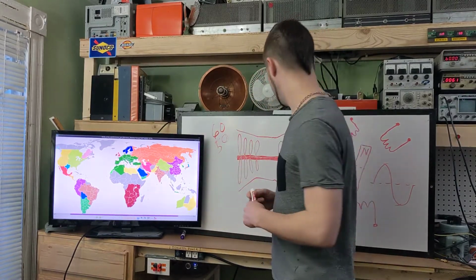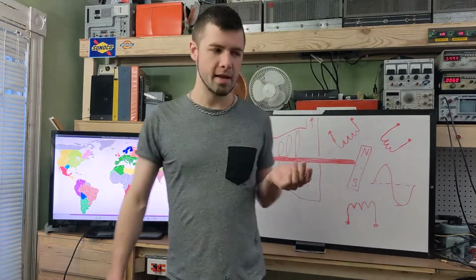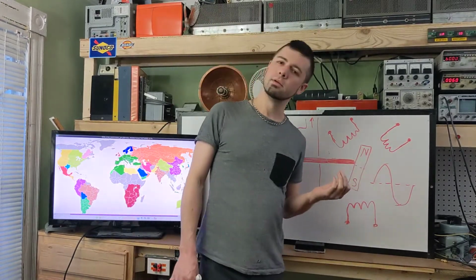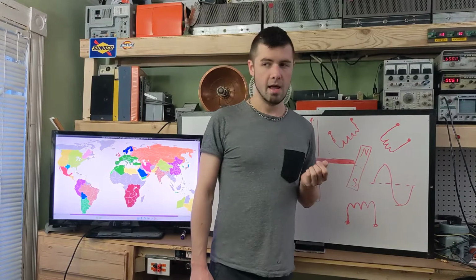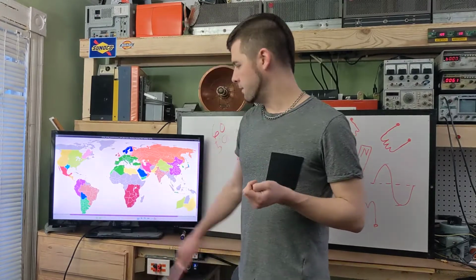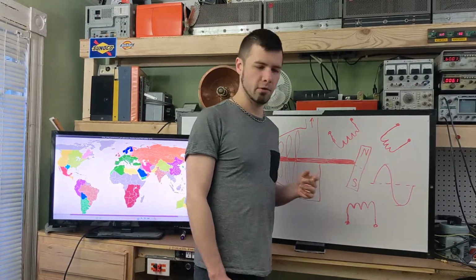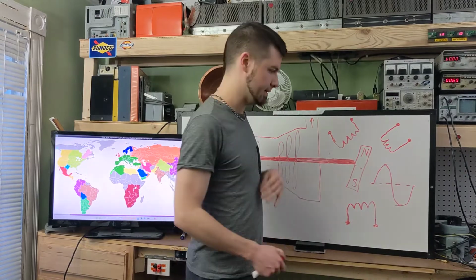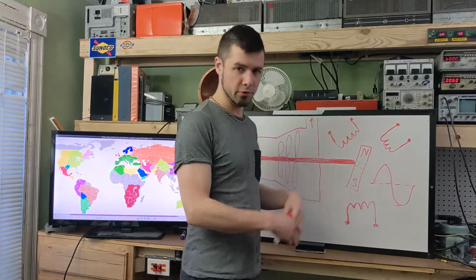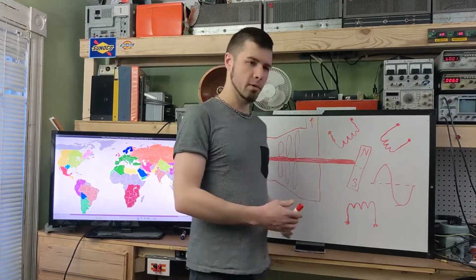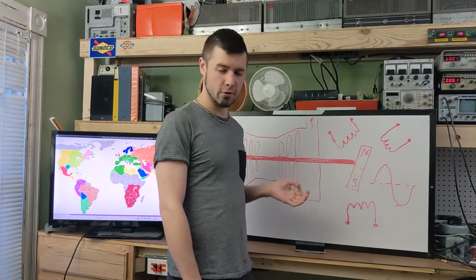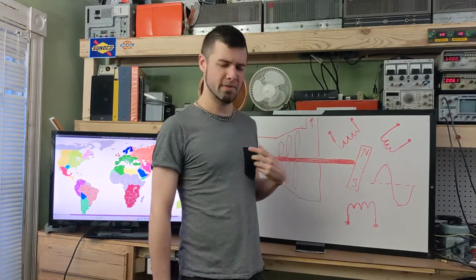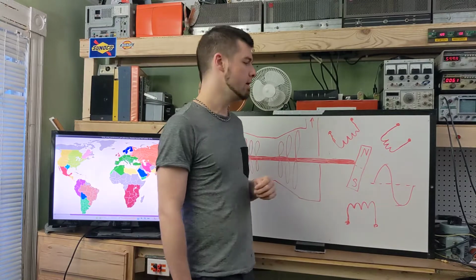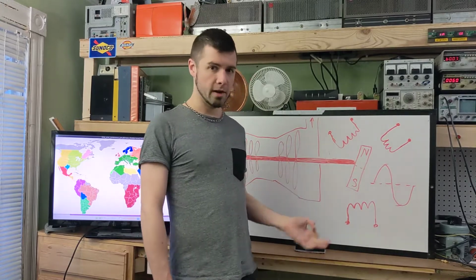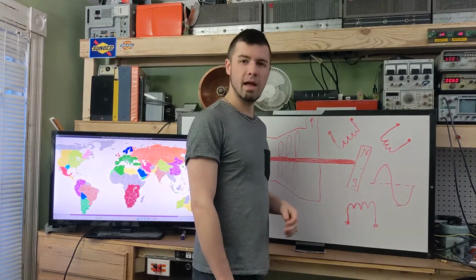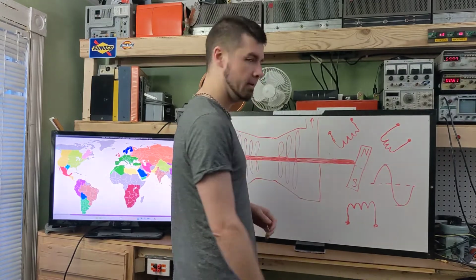How do they do that? Well, obviously somebody has to start the process, and the way they usually do it is what they call a black start. So there's a few power plants in the system that are designated to basically bootstrap the power grid. Usually they assign that role to a hydroelectric facility because they're very easy to deal with, and they're very good at starting without any kind of external excitation or influence.